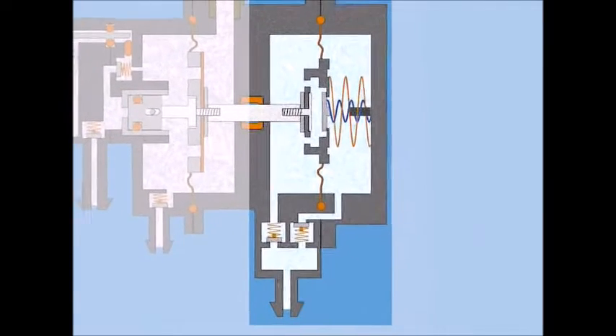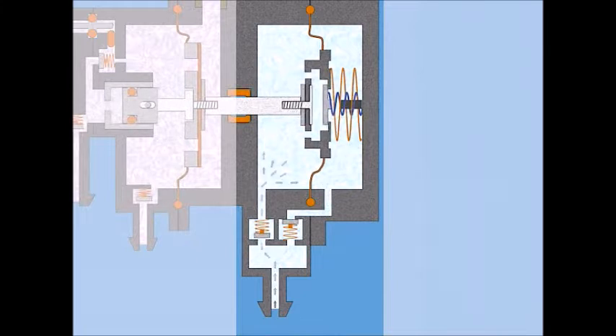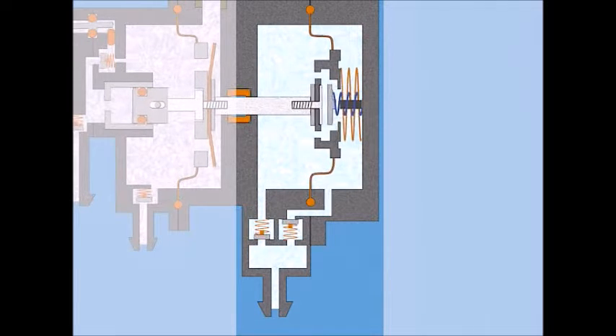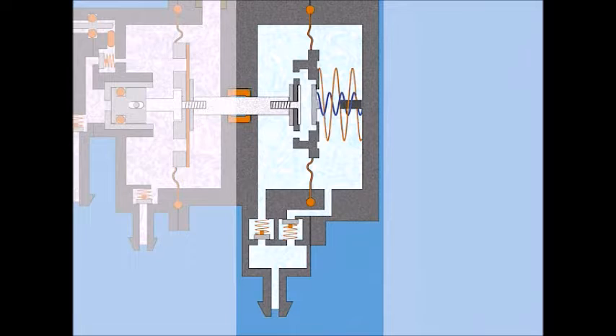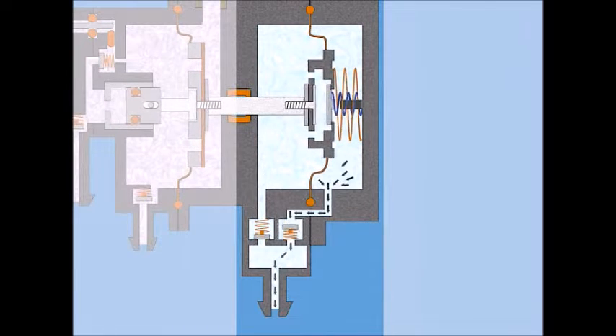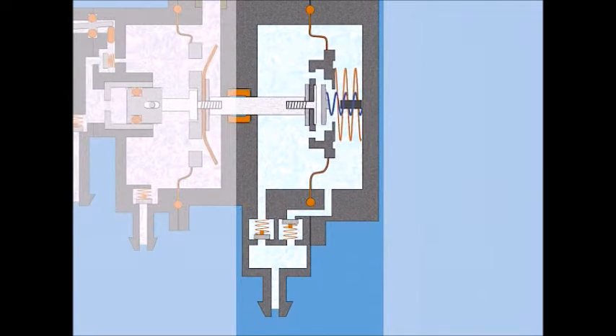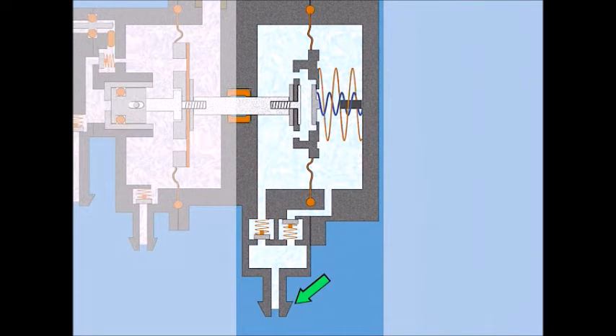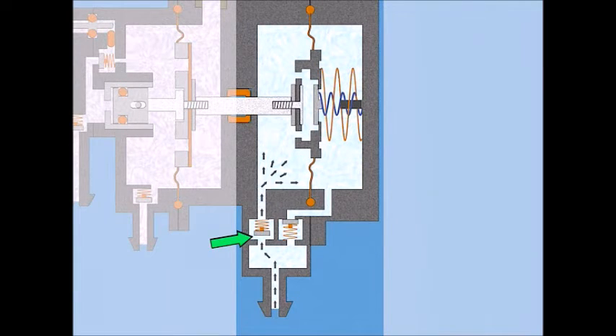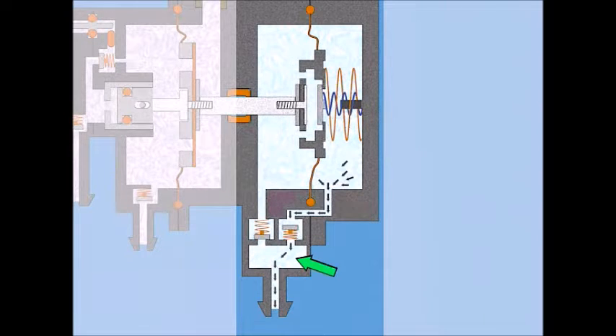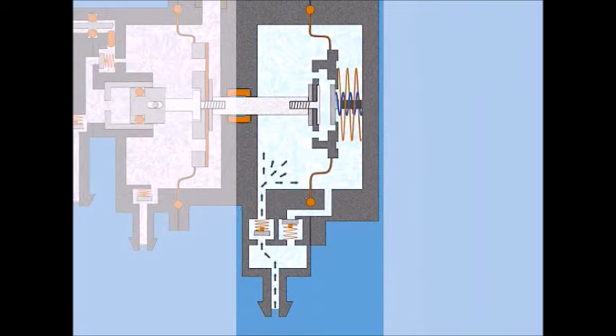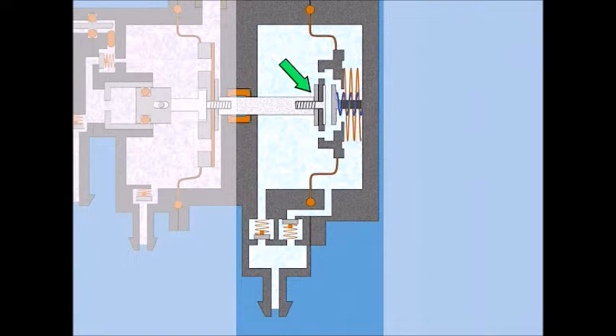Let's begin by examining the air motor. It converts pressure and vacuum pulses from the crankcase into mechanical motion to drive the fuel and oil pumps. Pressure and vacuum pulses from the crankcase enter the air motor chamber through a hose connected to the crankcase. Valves direct the pressure pulses to one side of the air motor piston. When a vacuum pulse is present, pressure is relieved from the opposite side. The pressure difference between the two sides forces the piston to the right, compressing the air motor piston spring.